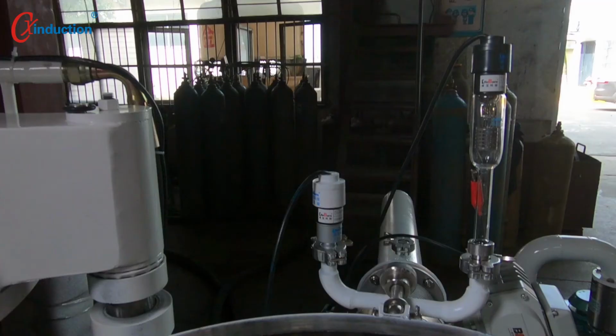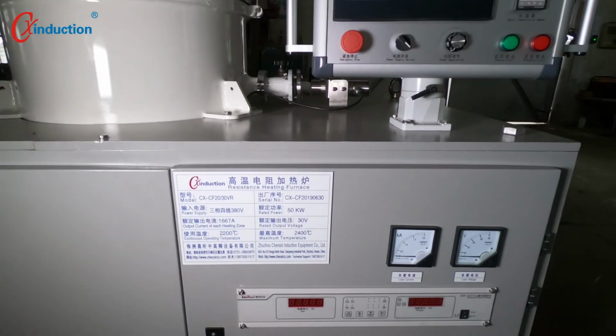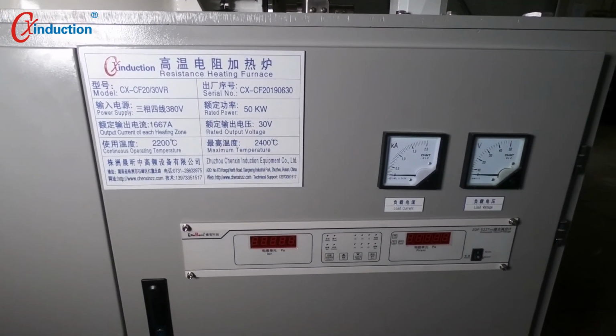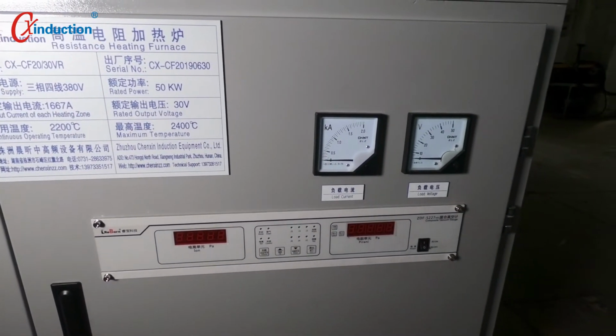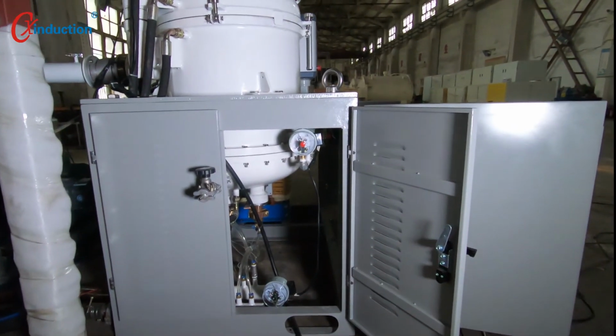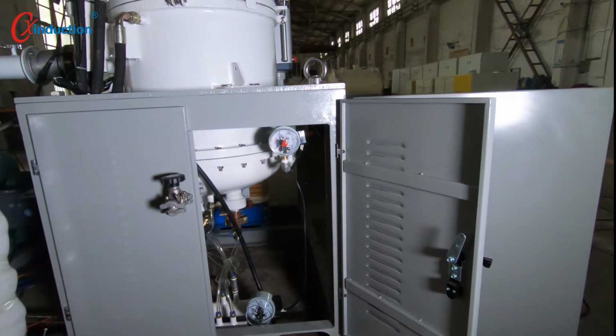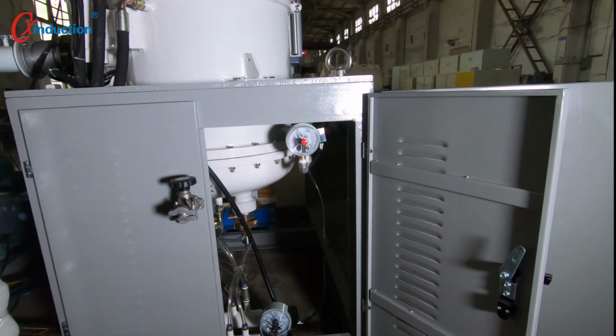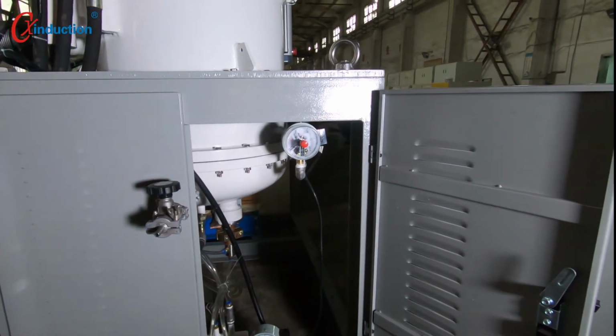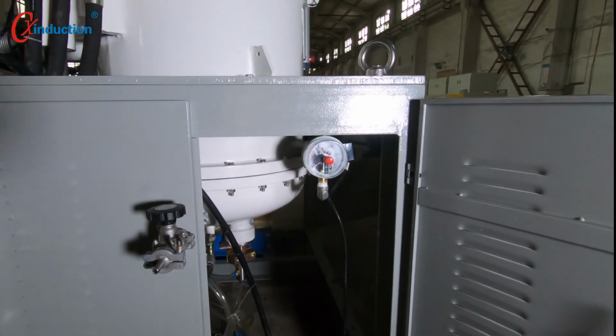A Pirani gauge and an ionization gauge are installed to monitor the pressure in the furnace, and the absolute vacuum reading is displayed on the composite vacuum gauge on the cabinet. On the furnace side, an electronic vent valve is installed, and a manual vent valve is also installed next to it, which can be used when the electronic exhaust valve fails.